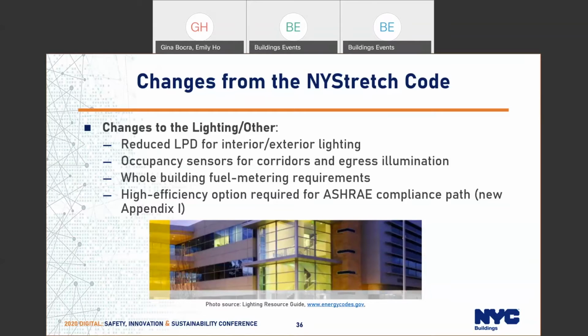There's now a new requirement for occupancy sensors in corridors and any sort of egress illumination. So essentially, the lighting has to shut off to the building code minimum illuminance value. So it's not a conflict with the building code. You still have to have a minimum level of lighting within the egress, but you cannot have full power lighting in your corridors and egress anymore. There has to be an occupancy sensor there that shuts it down to the building code requirement. So that's there now.